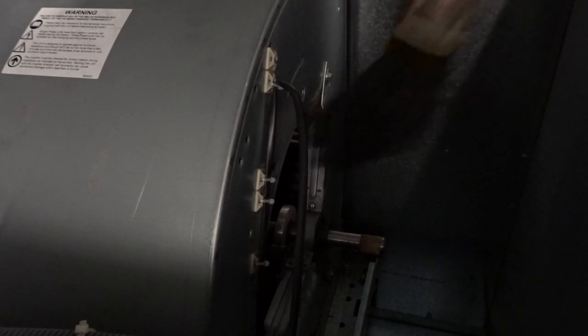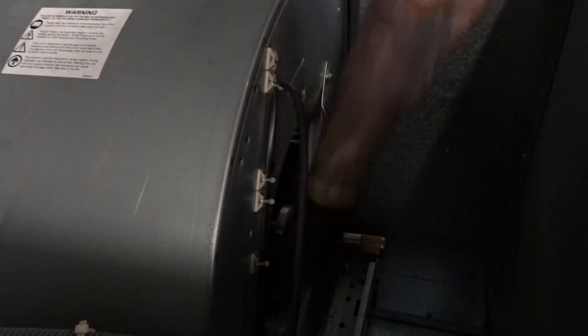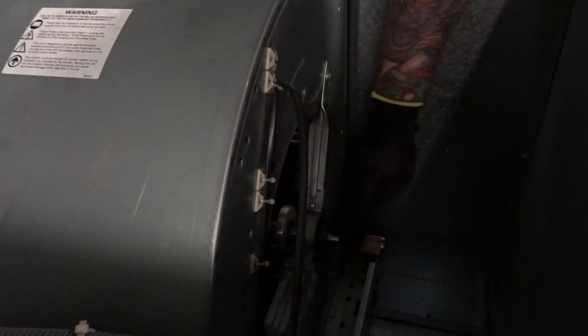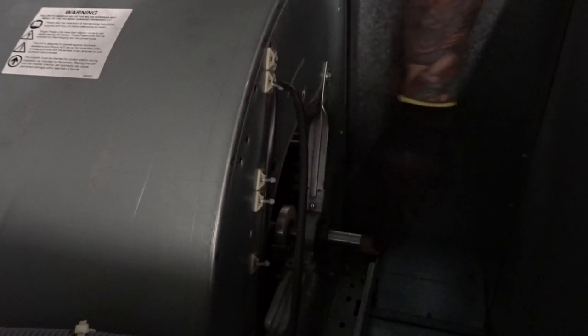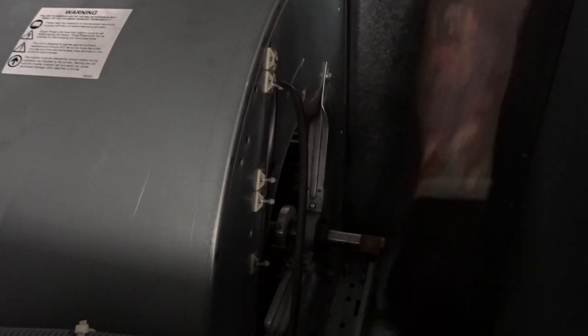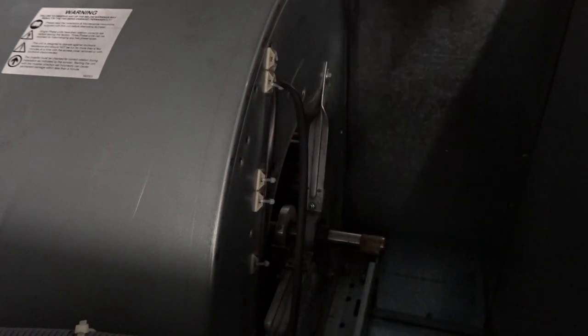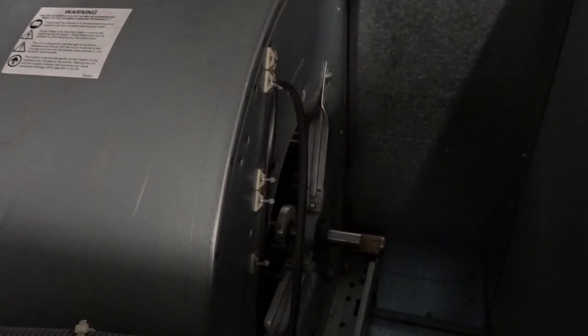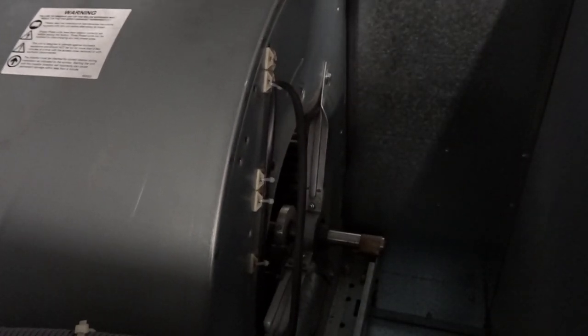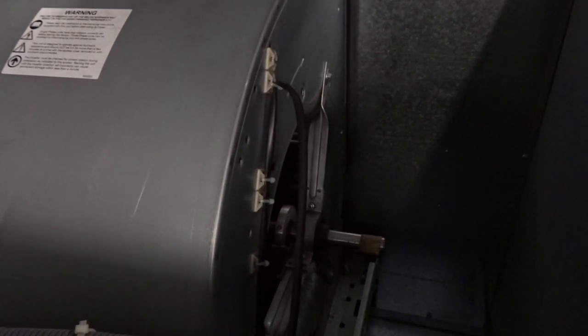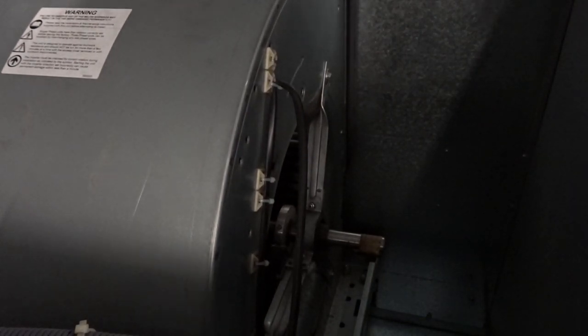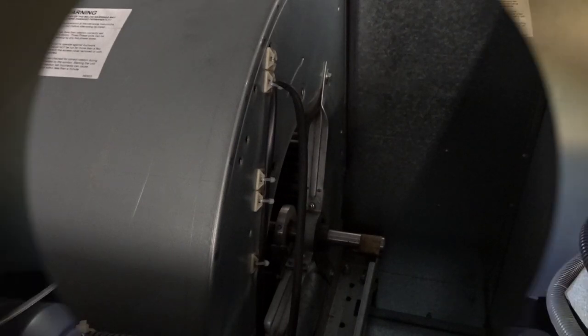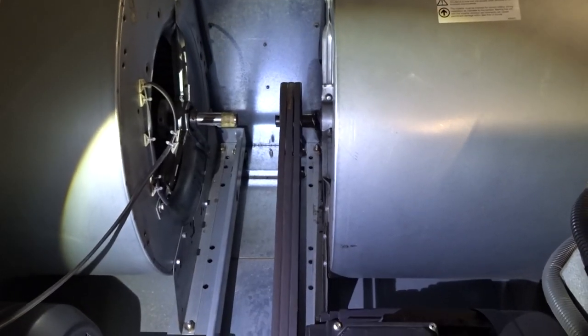Also checking the mounts that secure the fan mount, and also checking the mounting screws on the bottom of the fan housing to make sure that that's firm and secure, make sure there's no movement there.